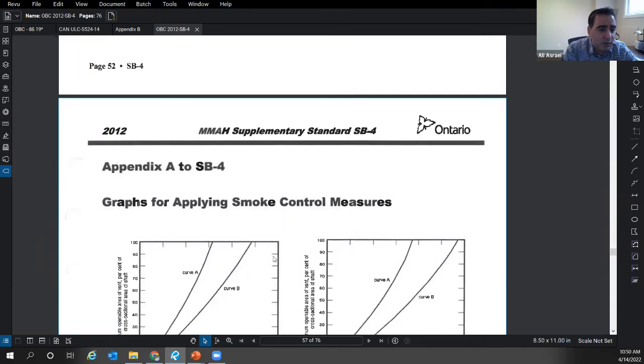And mostly, there are sprinkled buildings we're talking about, they're Measure A. So they asked to keep that sentence, to let everyone know it's just keeping the corridors and residential occupancies pressurized. So we don't shut down on any fire unless there's smoke in the duct, smoke in that fan. Other than that, we want those fans to be running all the time to pressurize those corridors. So if it's in contradiction with Measure M, I don't know what that is right now, because I have to review Measure M. But to me, that's not something that you should have in that building.